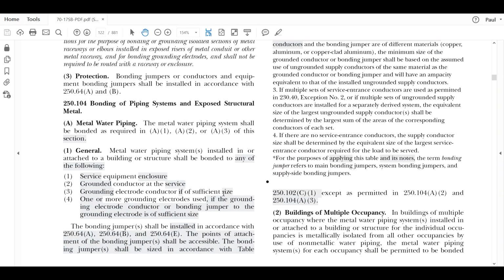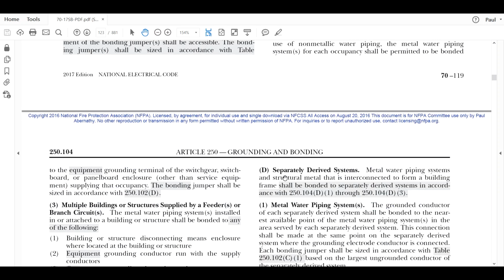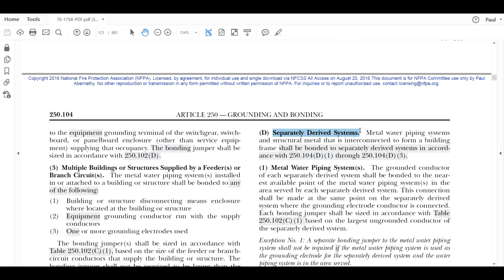All right, so 250.104, we're going to go down. So this is metal piping and exposed structural steel. The metal piping is not necessarily exposed, but it's the exposed structural steel. So it's both of those. We're going to go down to item D, and that is dealing with separately derived systems. That's what we're talking about. It says metal water piping systems. So if there are metal water piping systems in the area that's being served by that separately derived system, that transformer, and structural metal that is interconnected to form the building frame, shall be bonded. Okay. Now, that's the general rule.